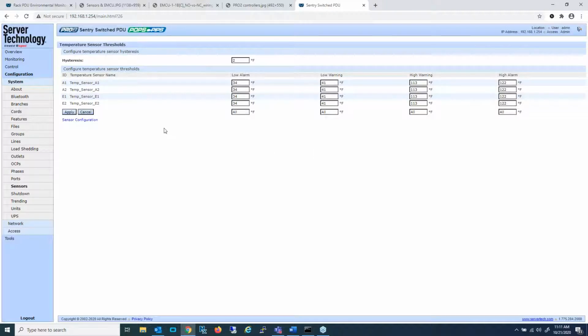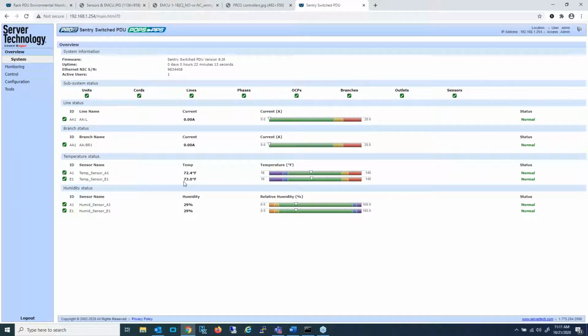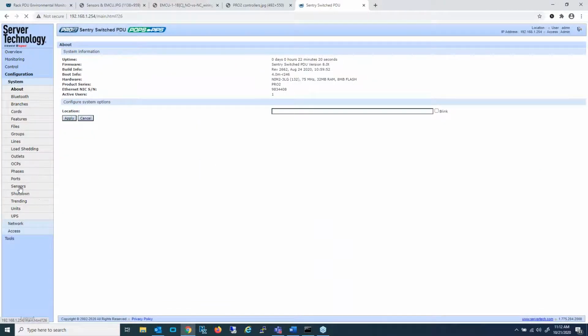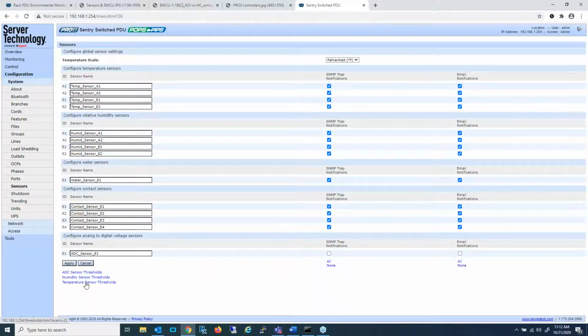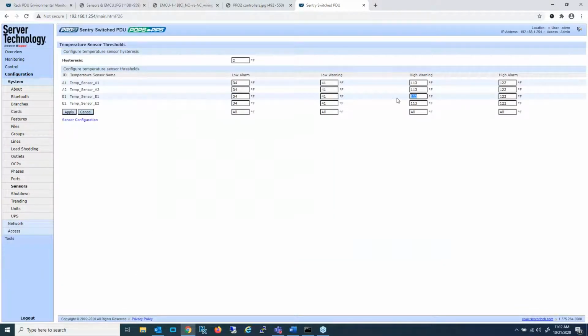Now, as a way to test that you will receive alerts if, for example, a temperature event occurs, one of the ways you can do that is to simply change the threshold for a sensor that exists. Let's take a quick look at what the sensor is currently reading. We've got 73 degrees for the sensor attached to the environmental monitor control unit. I'm going to go to sensors, go to the thresholds, and for that, I'm just going to set the threshold to be less than the current measured temperature.